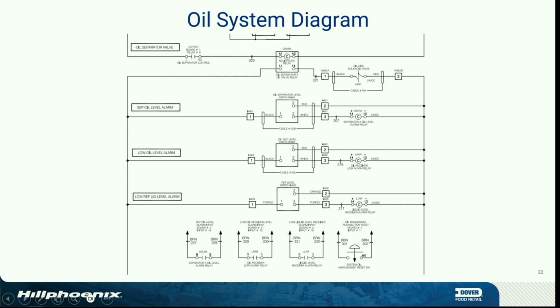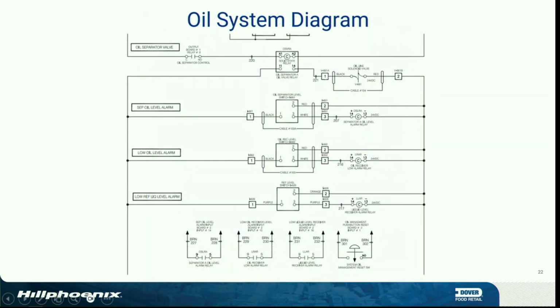Then we switch our number 3 leg on when the fluid's present. That energizes our OSLRA relay. That's a 24-volt coil relay. What that does is make an input into our control system to tell us we have fluid present in our separator. So we want to move it, right? We have 2 different voltages there. We can't put 24 volts into most any control board, right?